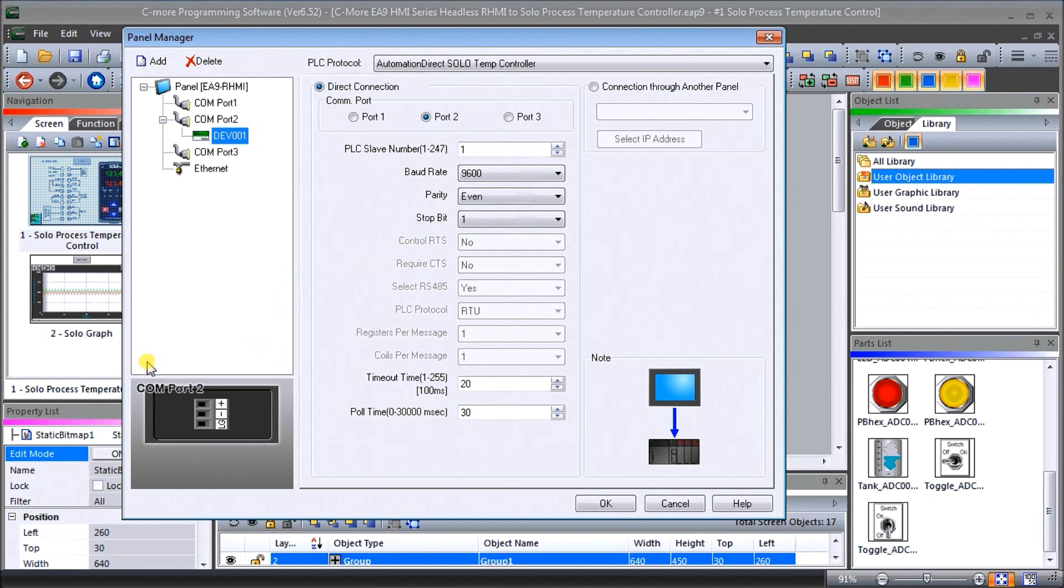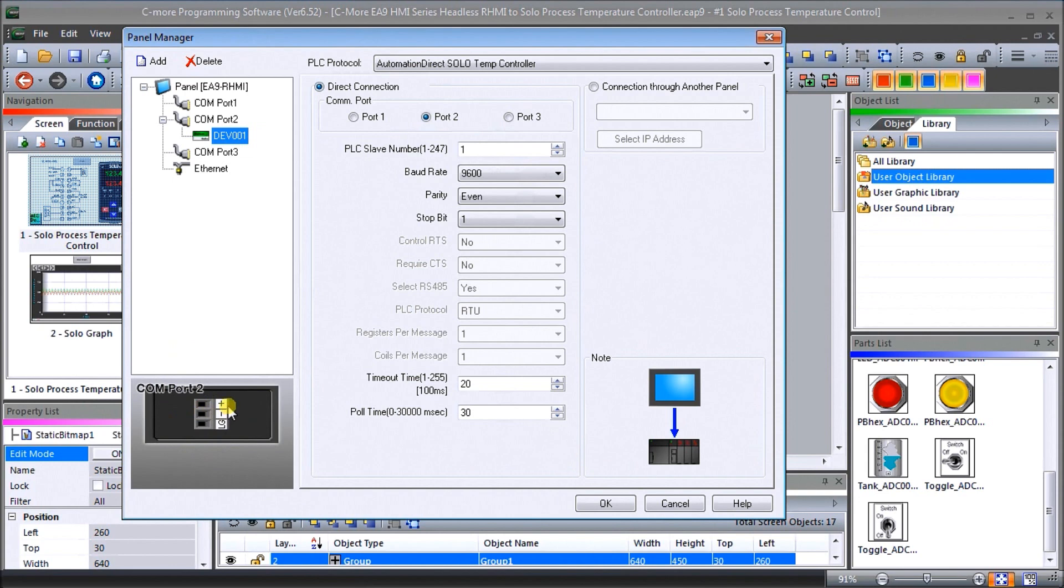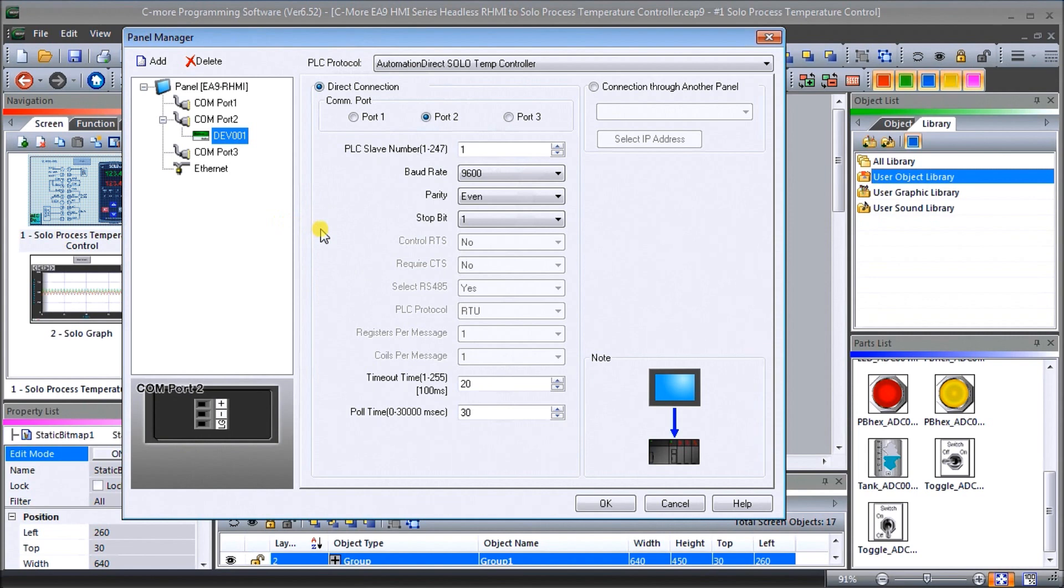Now this must match exactly the same protocol parameters as what we have in our solo process temperature controller and this actually uses our COM port number two which is RS485 so you can see here and we can actually add up 32 solo units to this system configuration. So 32 onto our network that we can grab information from.